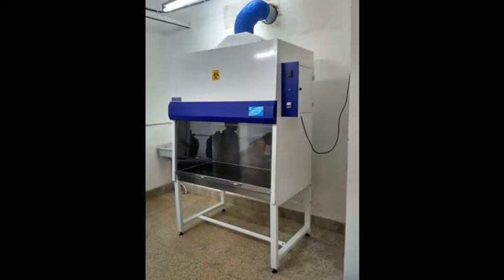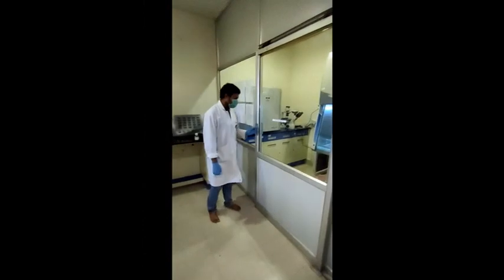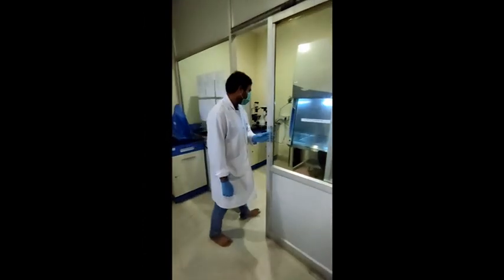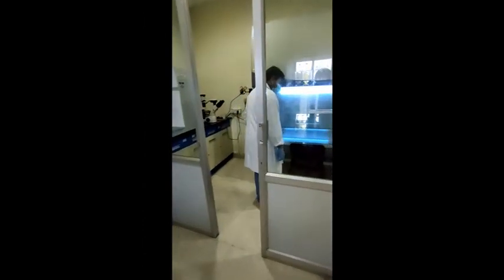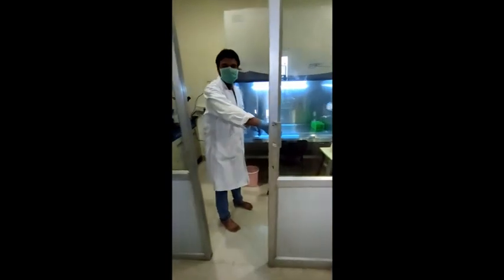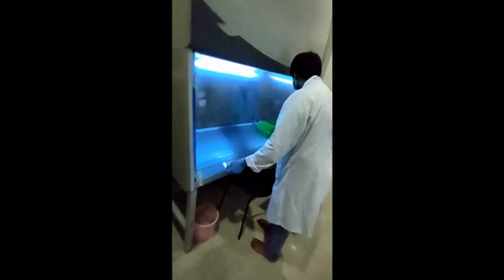Now we will be moving to our next equipment, that is biosafety cabinet. While entering into the laminar airflow area, always close the entry doors one by one, stepwise, which will maintain the positive air pressure inside the working area. Then you can see the UV light on. So before starting your work, put all your stuff inside the biosafety cabinet and turn the UV light on.